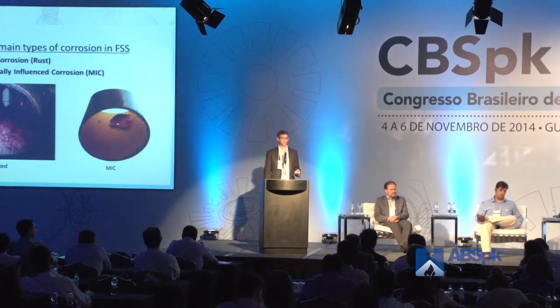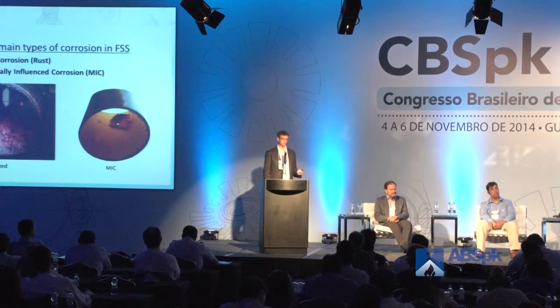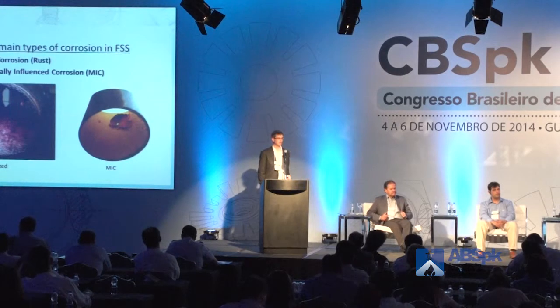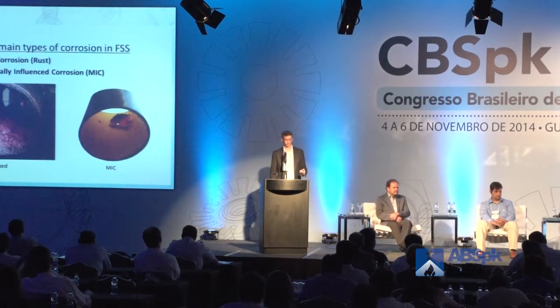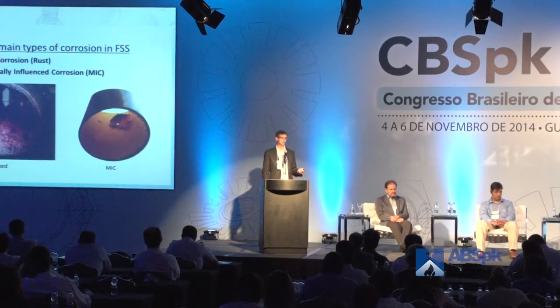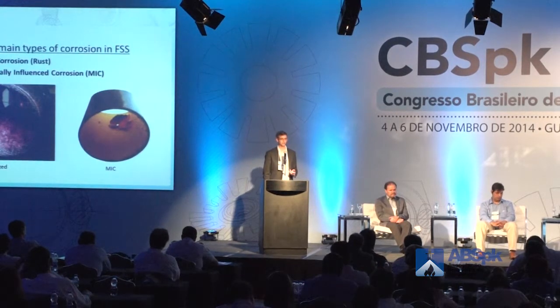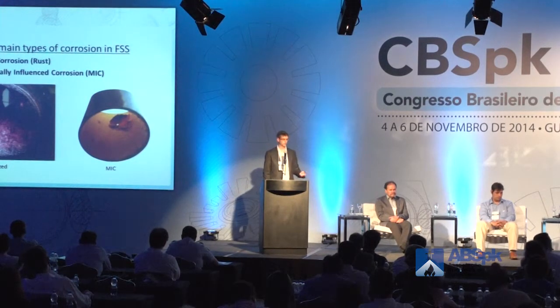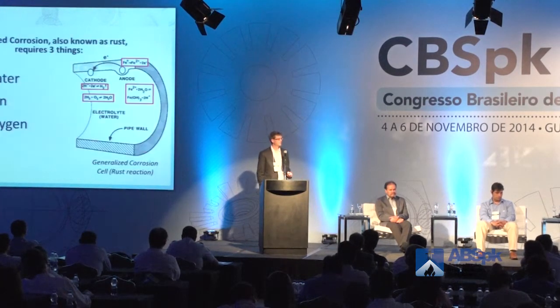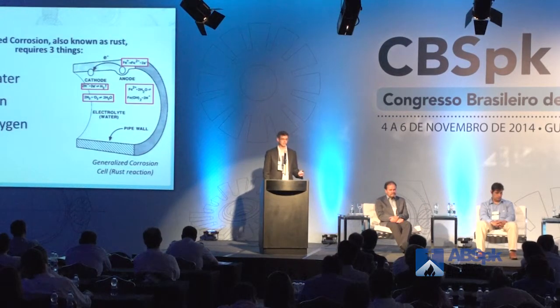So corrosion is a wide, significant problem that we're dealing with in the US, Europe, Brazil, everywhere. The main question I get is, what's causing the corrosion in the fire sprinkler system? Well, there are two different types. There's generalized corrosion, which most people call rust, and then there's microbiologically influenced corrosion, also known as MIC. It's kind of a buzzword in the sprinkler industry. Generalized corrosion is basically what you have when you have water, iron, and oxygen.